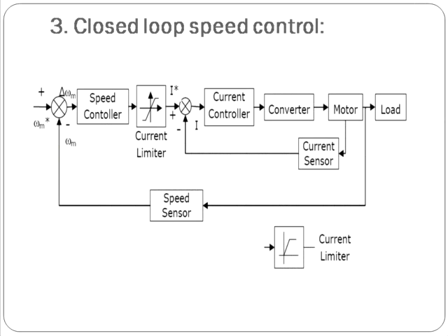The third scheme is closed loop speed control, which is the most widely used closed loop speed control method in electric drives. It consists of two feedback loops: an inner current loop and an outer speed loop. The current loop controls the converter and motor current to a safe limit, reduces the effect of any non-linearity present in the converter-motor system, and responds to increases in speed reference.